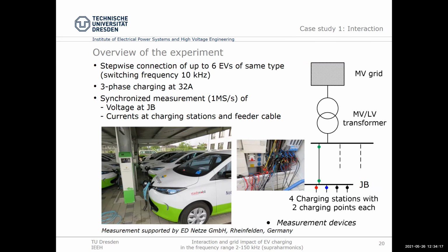On the right side you can see a layout of the situation. We have a medium voltage network in the upper part, then the medium to low voltage transformer - if I remember right, a 630 kVA transformer with 4% short circuit voltage. Then a dedicated feeder to a junction box, about 50 meters. At the junction box, there were 4 charging stations with 2 charging points each connected. We installed several measurement devices, all capable of measuring the frequency range up to 150 kilohertz, at the 4 different charging stations. Unfortunately we weren't able to measure each individual charging point, or at the beginning and end of the feeding cable.